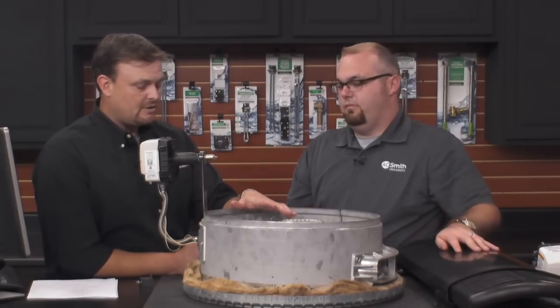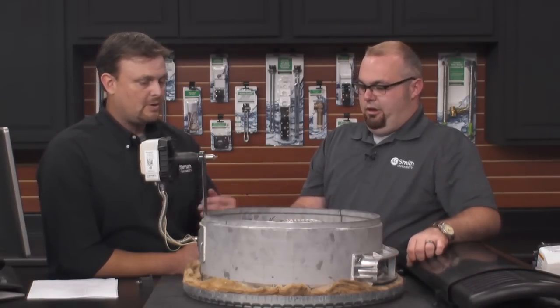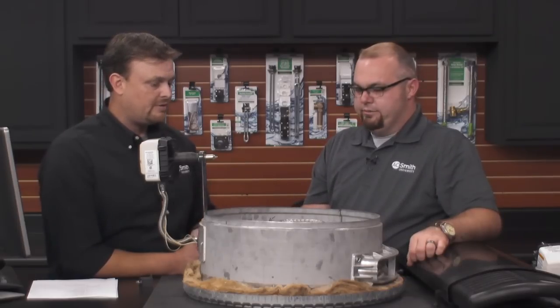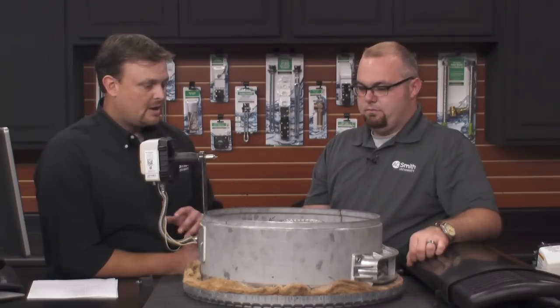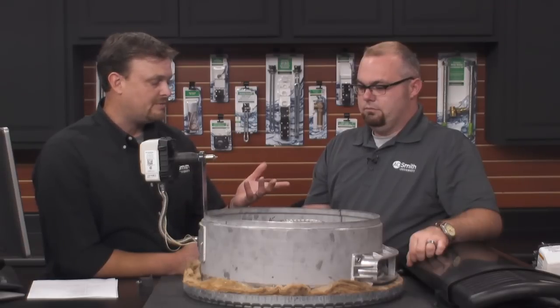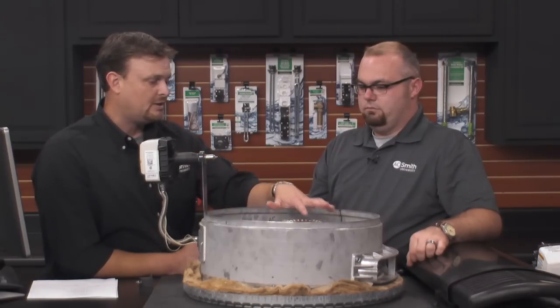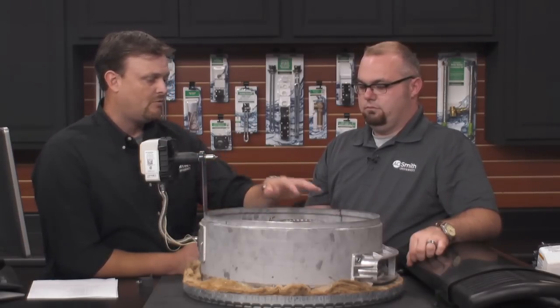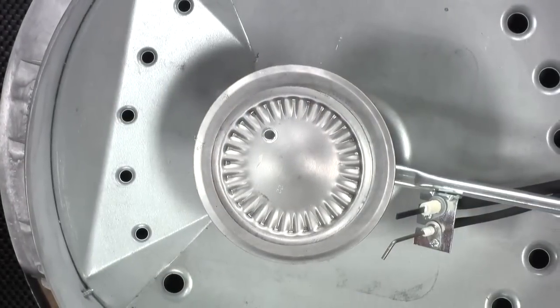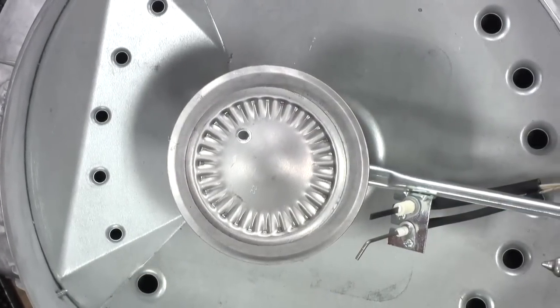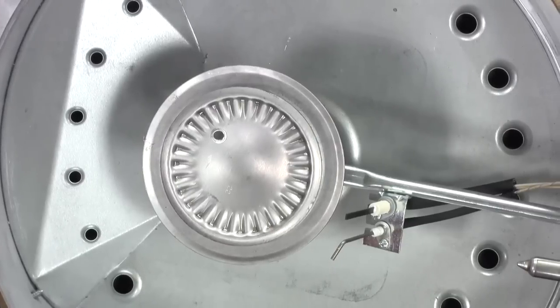Since we have the combustion chamber up here, we can talk a little bit about the burner and the ignition system. The first thing that looks different on the burner is we've got a little hole there. What's the hole for on the burner? Well, this is a more efficient power vent. It's not a condensing power vent, but it is more efficient.